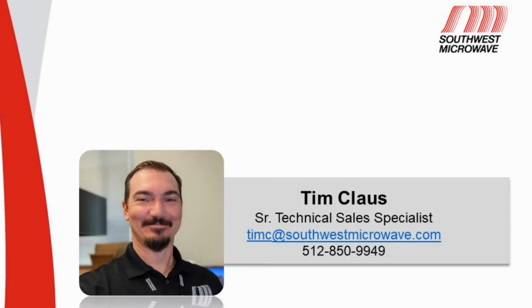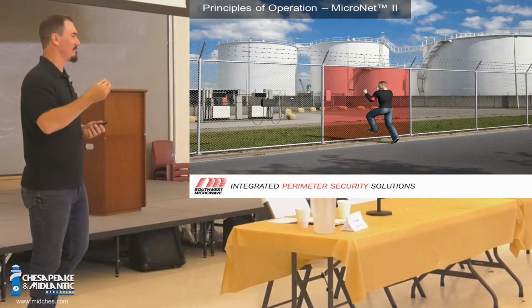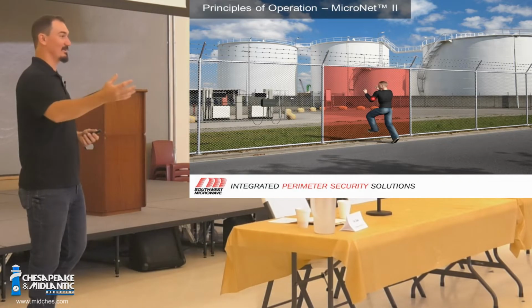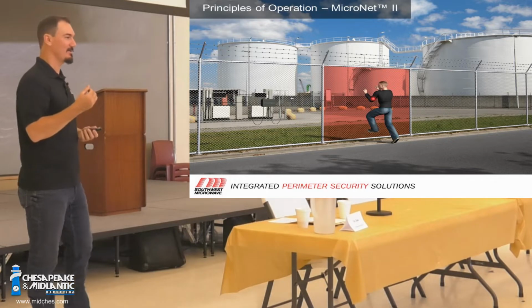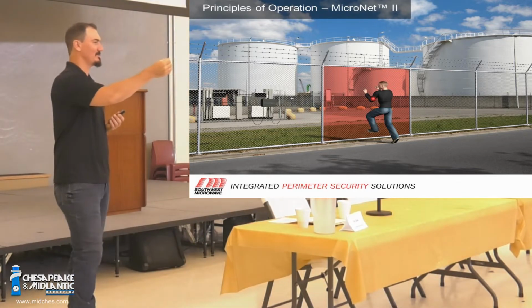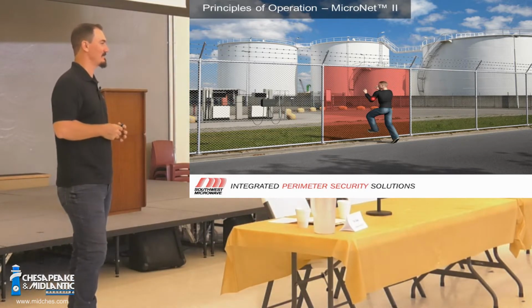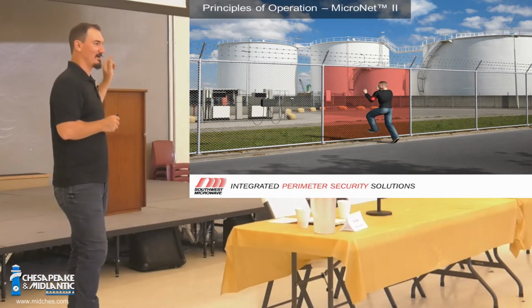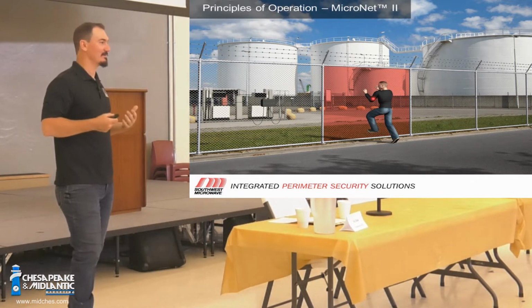So think of it just like a radar system out in the open air, right? An airplane flies by through the radar. If it's a small plane, it sends a small reflection back. If it's a really big plane, it sends a really big reflection back. And not only can you tell the distance to that object, but you can tell the size of it based on that return pulse. Our fence-mounted sensor, the MicroNet system you use, is exactly like that.